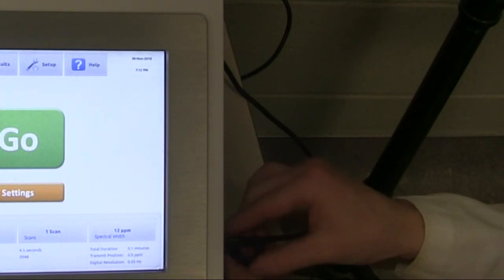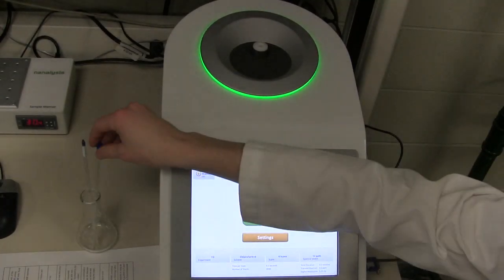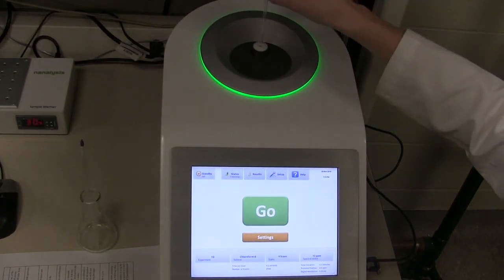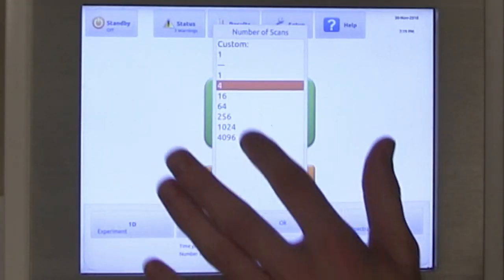Insert your USB stick into the port on the right side of the instrument. Insert your sample NMR tube. Set the number of scans and then press go to start the measurement.